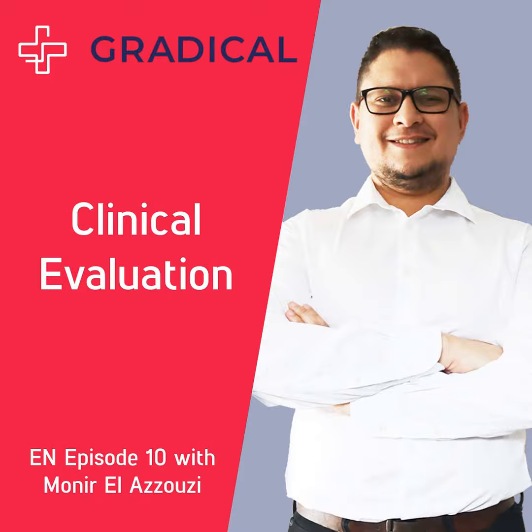Now you have found the patients, you have the right centers where you can do this clinical investigation. Then you are using your device on the patient. For example, if it's an implant, you have to go through a surgery, you place the implant inside the patient, and then you wait to see if the patient has recovered and is doing well. So the idea of the clinical investigation is not that as soon as you do the surgery, it's a success, it's over. You also have to do a follow-up. You say, okay, now day 0, we have done the surgery. Let's do a follow-up after 2 weeks. Let's do a follow-up after 1 month. Let's do a follow-up after 3 months. Let's do a follow-up after 6 months, etc.